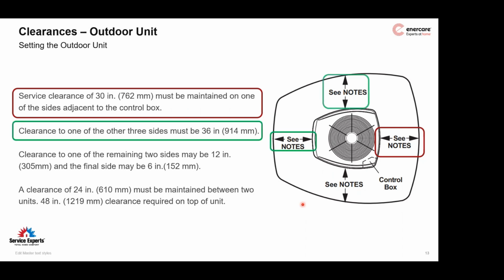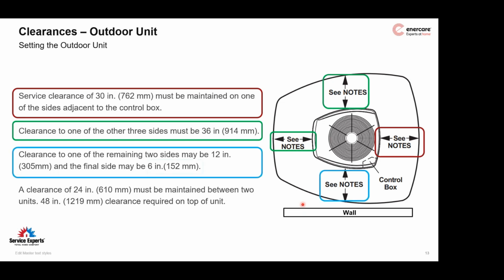So I'd take the 30-inch from the backside, and 36-inch on one of the open sides in between the house, if it's not a side discharge style. You can have as little as 6 inches to the wall for this unit. Specifically, this is the Lennox, that kind of oblong shape. And then, of course, on top, a minimum clearance of 4 feet. Nothing too earth-shattering here. For whatever the manufacturer is requesting for service clearances and airflow clearances, please make sure that we're following their suggestions.